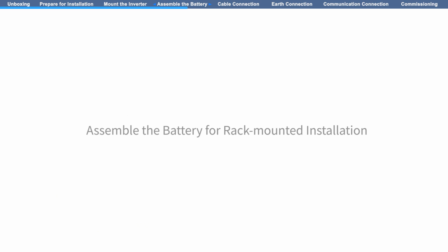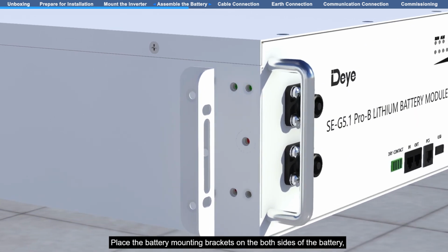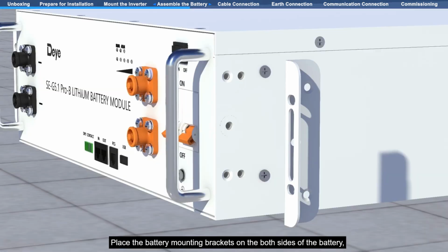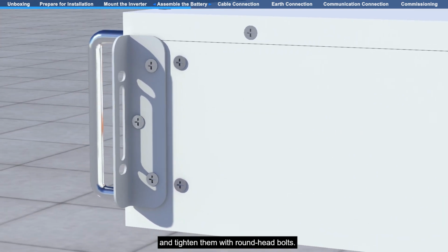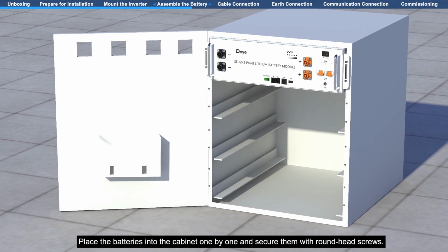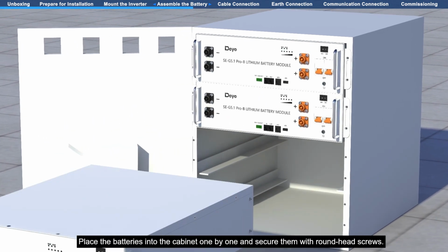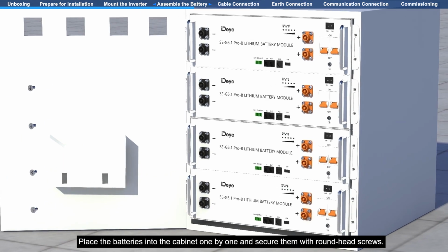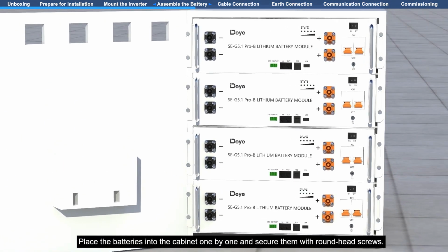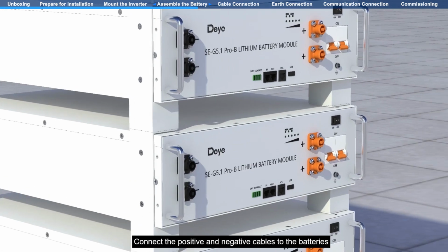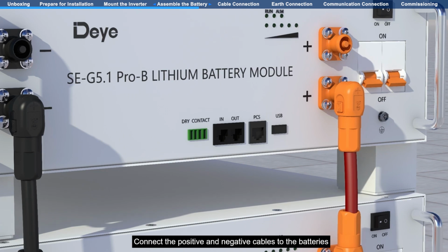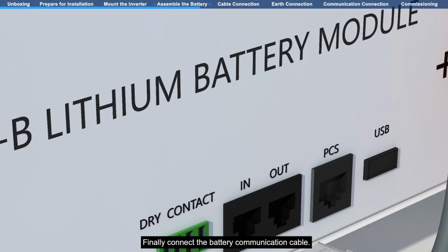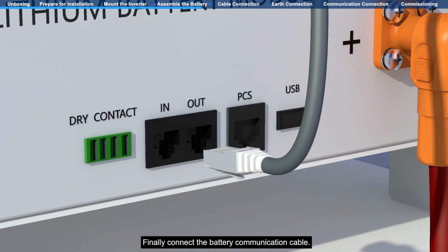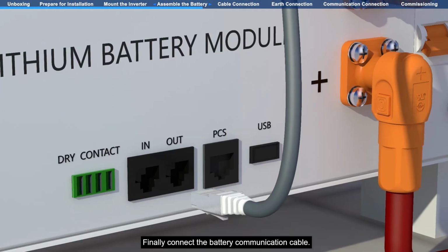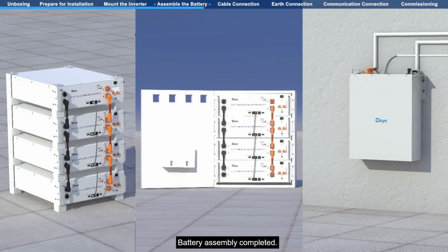Assemble the battery for rack-mounted installation. Place the battery mounting brackets on both sides of the battery and tighten them with round head bolts. Place the batteries into the cabinet one by one and secure them with round head screws. Connect the positive and negative cables to the batteries. Finally, connect the battery communication cable. Battery assembly completed.